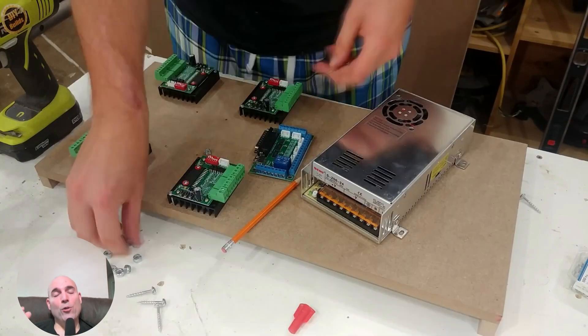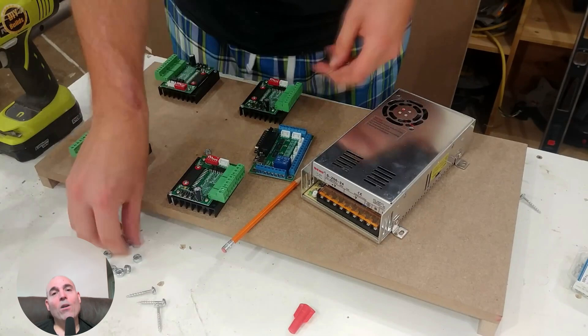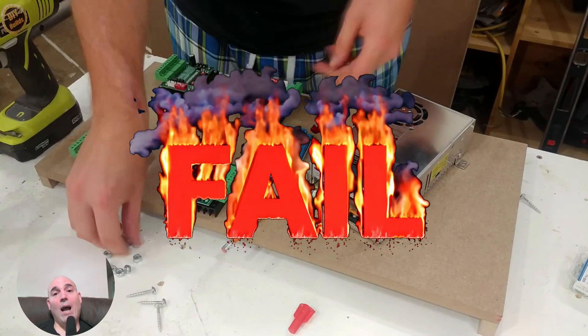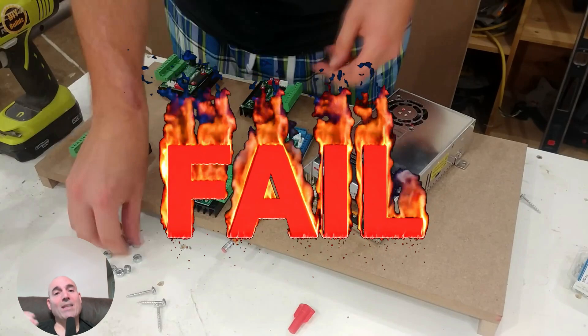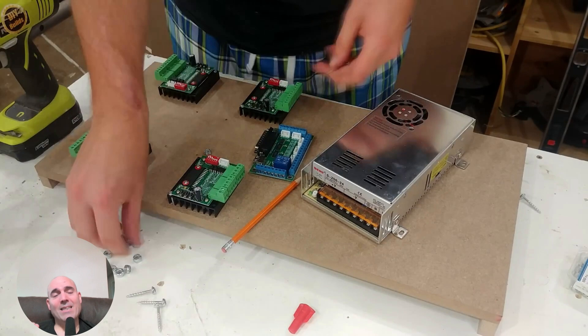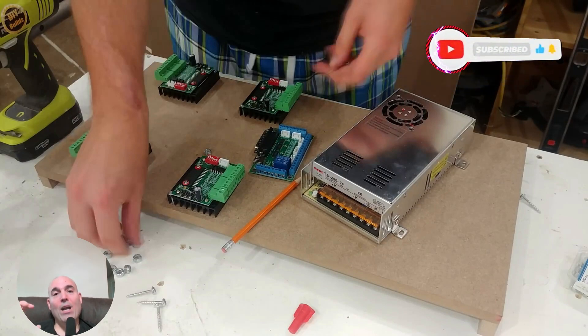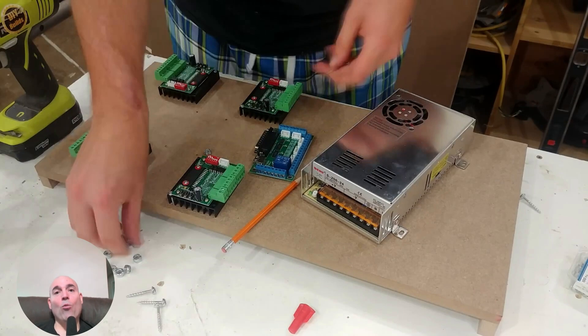And because of course, as I've stated in many previous videos, God forbid something ever happens. You are then using the proper substrate for an electrical enclosure. Number one, it would be up to code. And number two, if an insurance inspector ever came in, God forbid that there was a fire, you would get paid. Think about what I'm saying. I do not know why these guys continuously are doing this. I don't know why it's slipping through the cracks. And now, of course, YouTube's algorithm is getting smarter, but we need to be smart as a community and look at this and say, this is bullshit. It should not be seen online where a guy is promoting using wood at all around his electronics to encapsulate them.